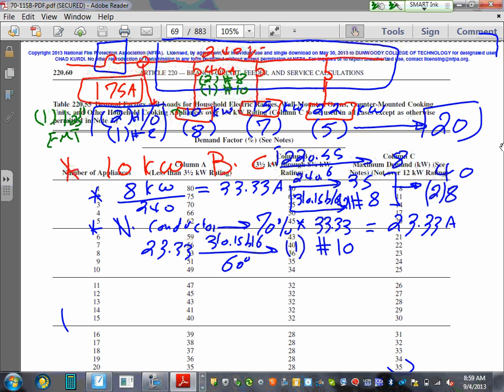220.61. If you go to the 220.61 section, it will tell you your derated ranges neutral and the dryers neutral by 70%. What? This one for any neutral, as a matter of fact, for ranges, it doesn't apply to, I don't think it's... good question. I always apply it. Can you guys look? I don't think there's a household ranges. Okay, go to that one. Read it. I can't remember.